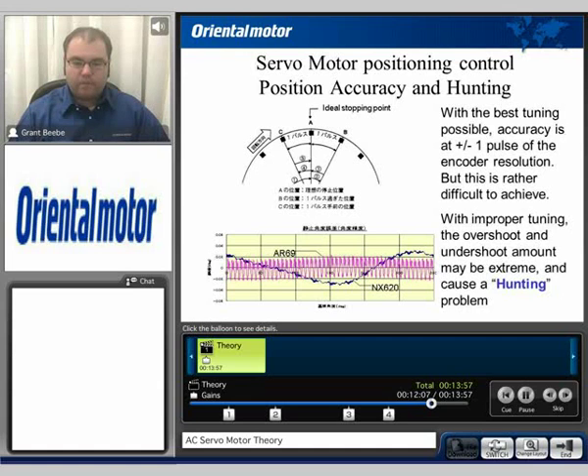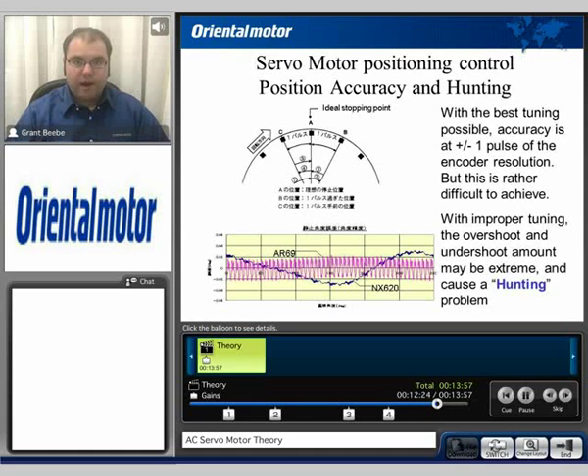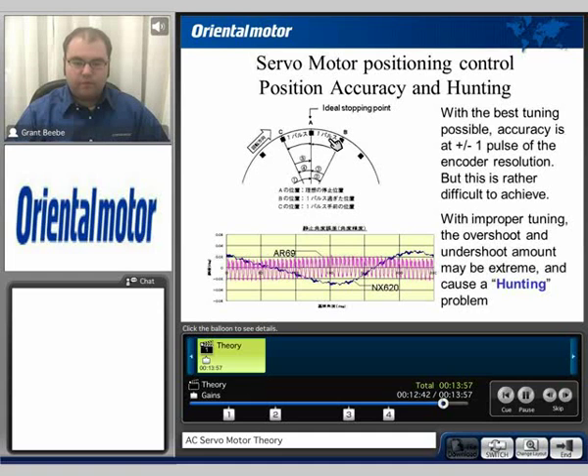Also notice there's another phenomenon you may encounter with a servomotor, which is called hunting. Basically, when the gains are set too high, it might actually oscillate back and forth within one pulse. With the best possible tuning, accuracy is always going to be plus or minus one pulse of the encoder resolution, and in some cases that can be pretty difficult to achieve. When the gain is set too high, it may actually oscillate back and forth between one pulse — so instead of stopping specifically on point A, you might go back to B, overshoot, go back to C, come back to A, and keep oscillating between these three points.